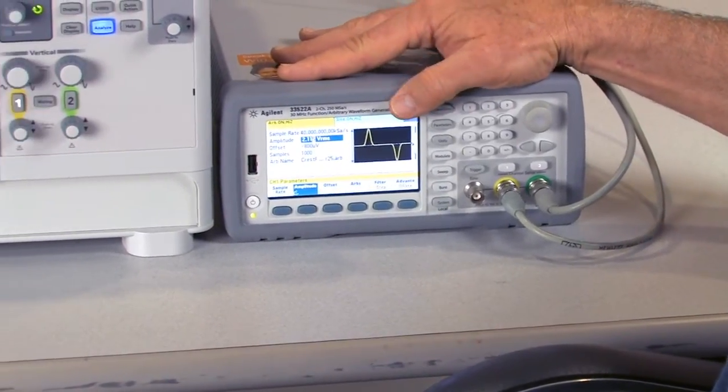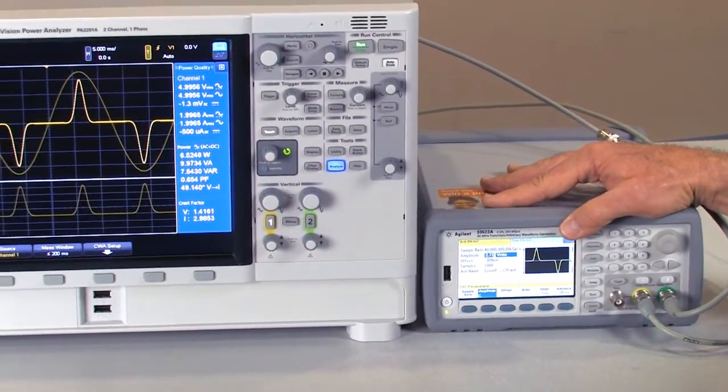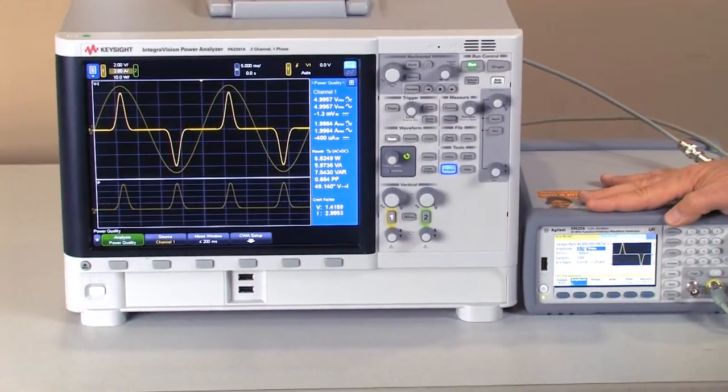Outputting the voltage waveform as a simple sine wave and simulating the current waveform as a high crest factor signal with an arbitrary waveform.